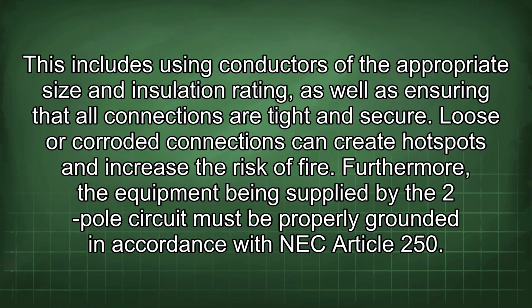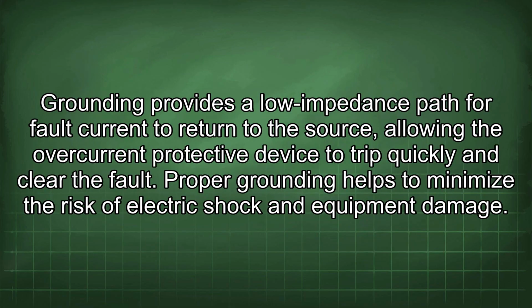Furthermore, the equipment being supplied by the 2-pole circuit must be properly grounded in accordance with NEC Article 250. Grounding provides a low impedance path for fault current to return to the source, allowing the overcurrent protective device to trip quickly and clear a fault. Proper grounding helps to minimize the risk of electric shock and equipment damage.